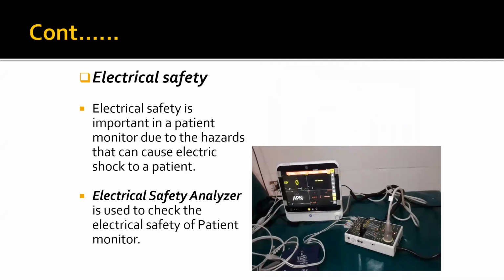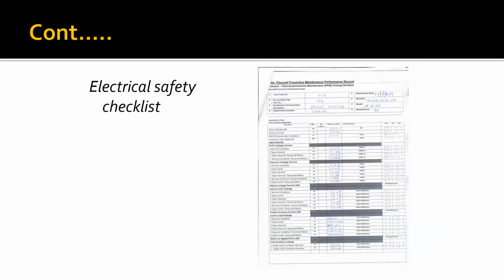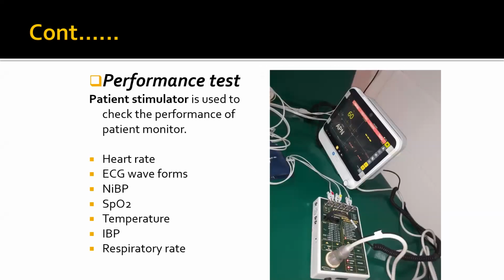So electrical safety: you do electrical safety first, after physical. You check that all the parameters of the electrical test have passed, and you check the ECG cable and all that. These are what the electrical safety checklists look like. You get so many readings, almost 21 tests there. For class 1 and class 2, the tests can vary between 21 and 16, depending on the probes that you're connecting.